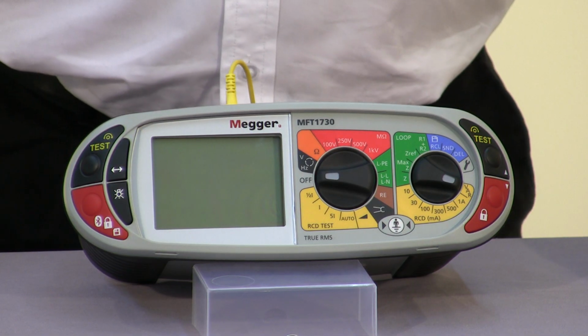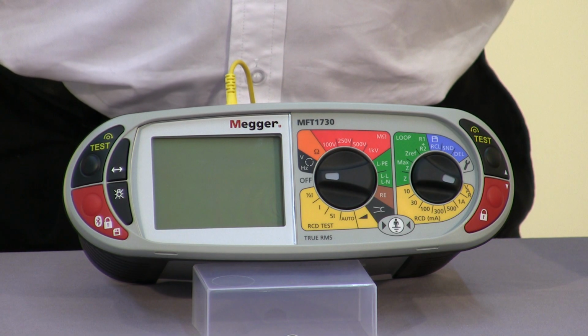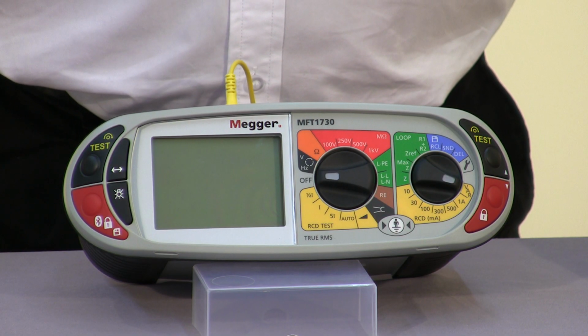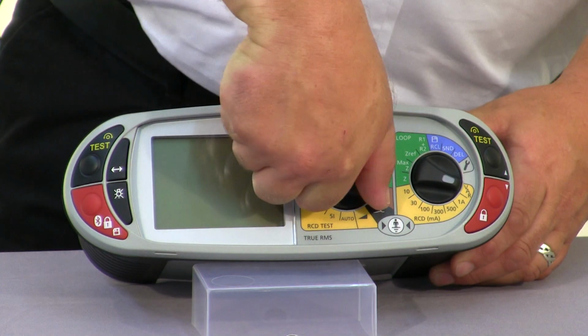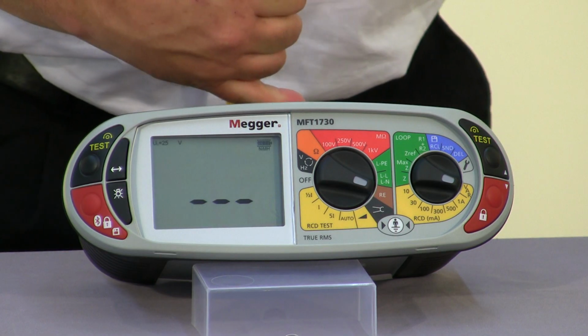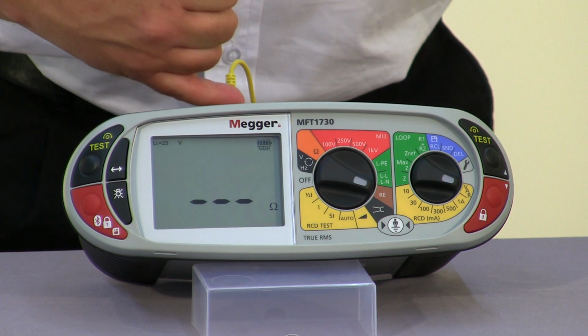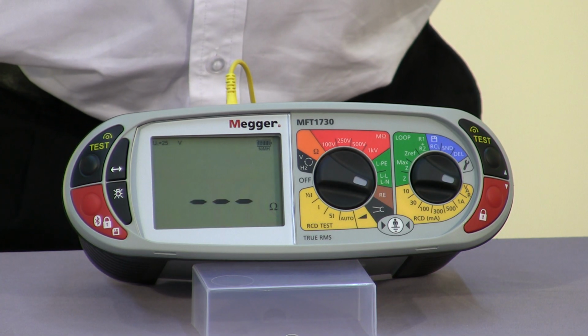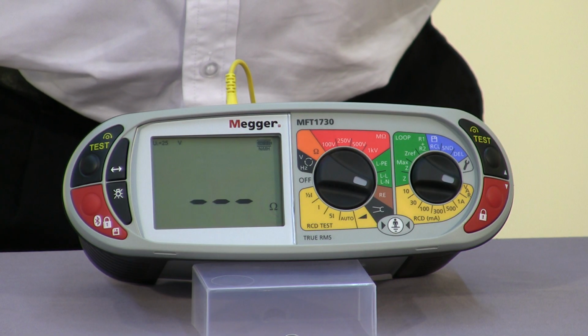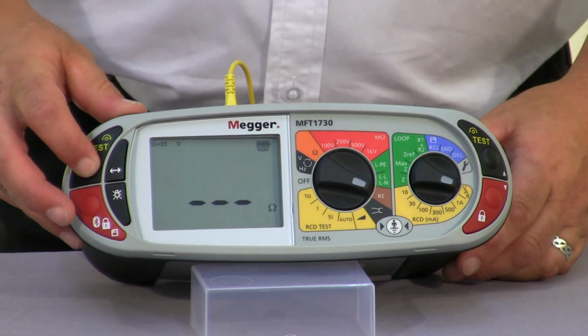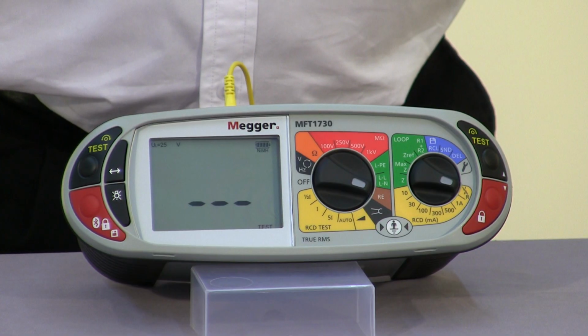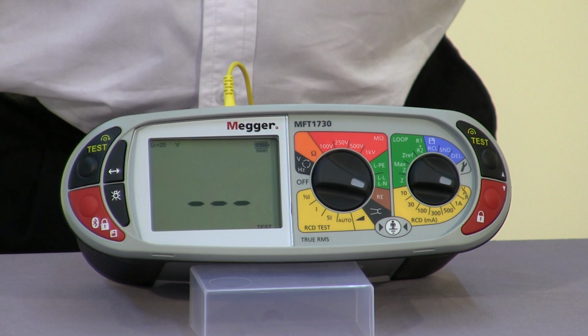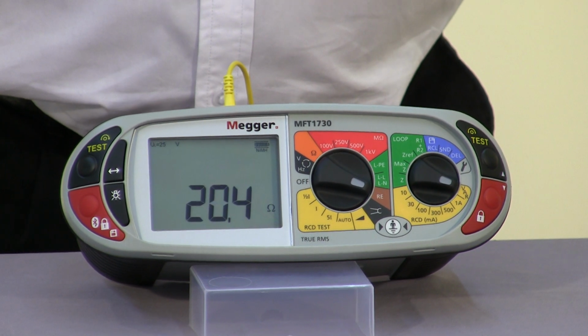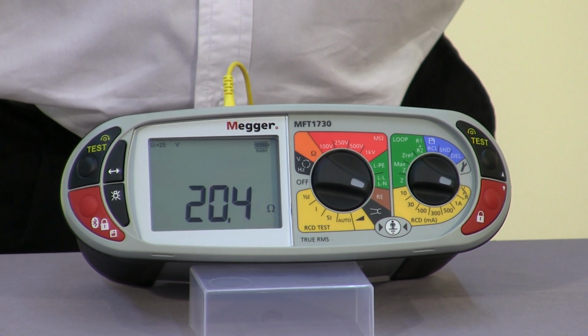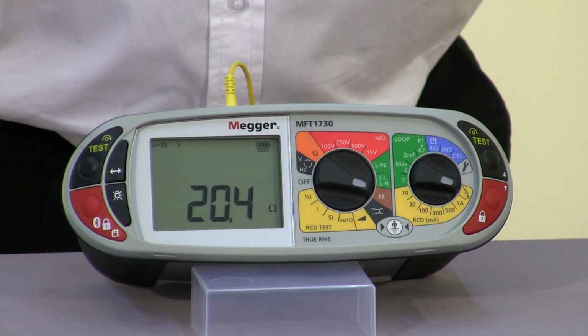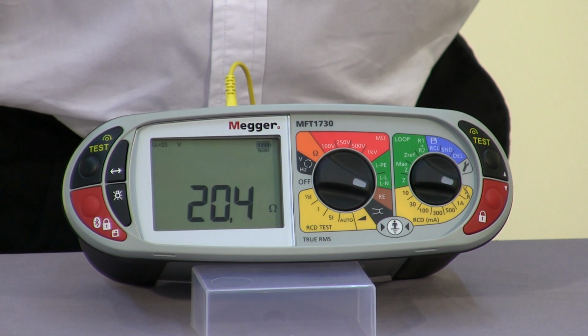The final test we'll look at is available only on the MFT1730, and that's our three-wire ground stake or earth resistance test. So as you can see, we've got our RE test range. Now, in the top of the unit, I've got a standard three-wire ground stake simulator connected via the three wires. So we have our earth rod on the green, our potential probe on the yellow, and our current probe on the red. So initiating the test sequence, one of the nice things about the MFT1730 and this ground resistance test is that in the event of having a high P2 or C2 measurement, the unit will come back and indicate that for you. So as you can see on the simulated earth we've got a reading of 20.4 ohms.